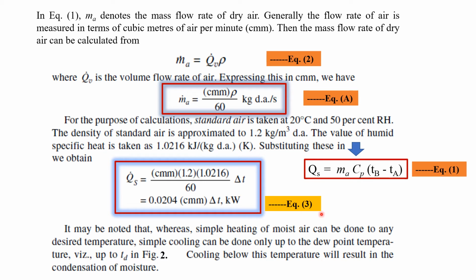So this is a very important equation, because with the help of this equation, simply by knowing the volumetric flow rate cmm and what amount of temperature change is required, we can know how much heat is either required to be supplied to the air or is to be taken away from the air, so that it undergoes either a sensible heating process or sensible cooling process. It may be noted that whereas simple heating of the moist air can be done to any desired temperature, as we have already discussed, simple cooling can be done only up to the dew point temperature, that is up to Td. Cooling below this temperature will definitely result in the condensation of the moisture.